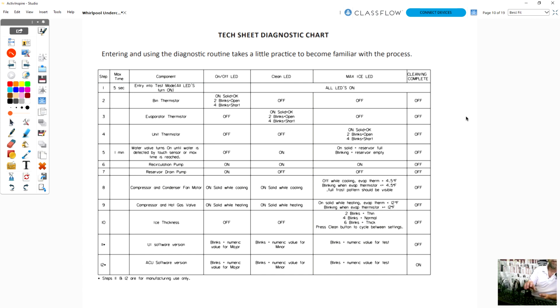You're only going to go into diagnostics of problems that you're having with that machine. If it's not filling, then I'm going to go over to the ice or the water fill valve right here, step number 5. If I had something with the ice thickness and I wanted to see what the setting of the ice thickness was, 2 blinks tell me that it's thin, 4 blinks normal, 6 blinks thick, and that up here at the very top is telling you the max ice.